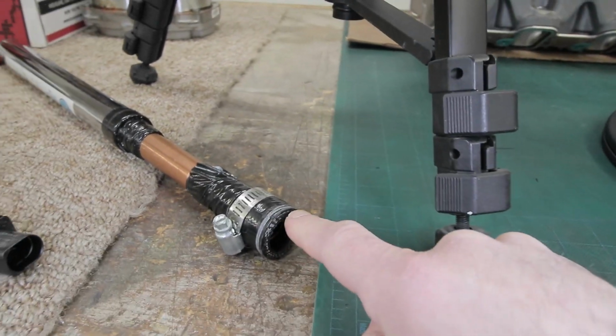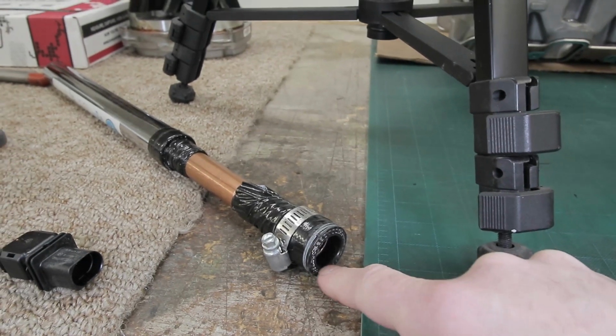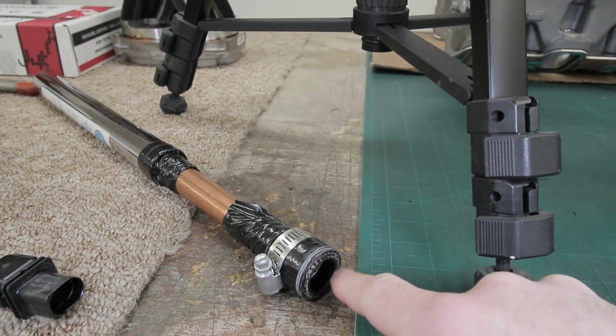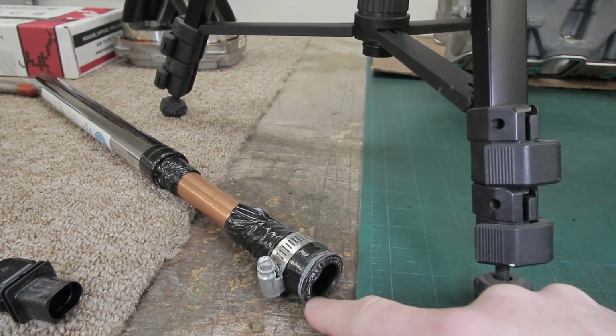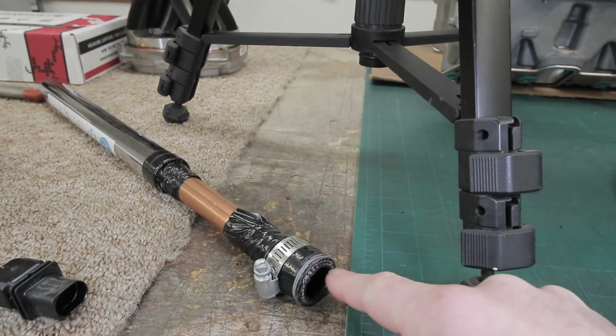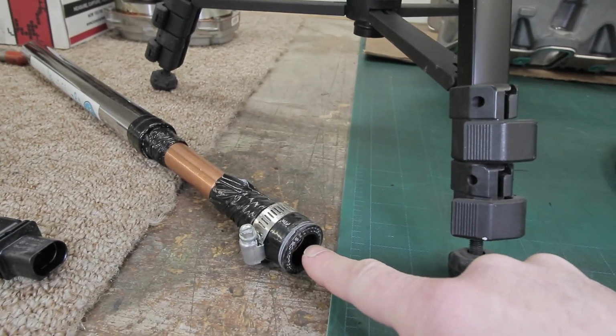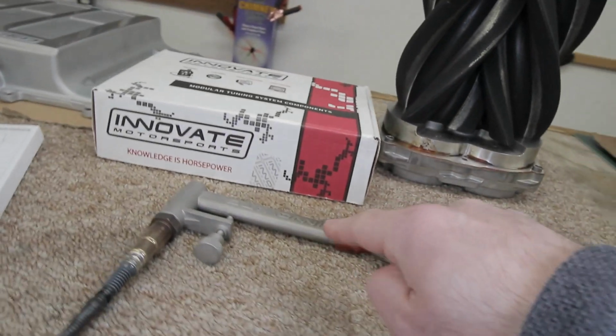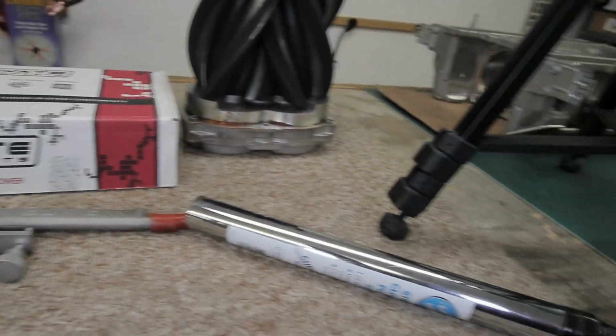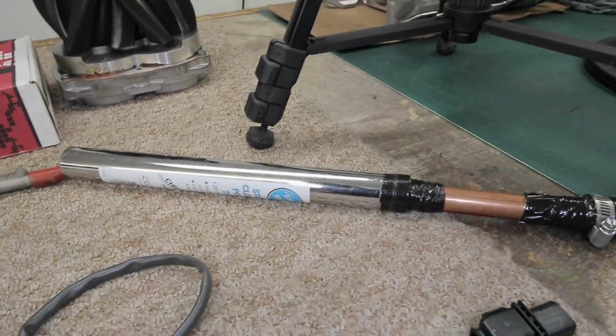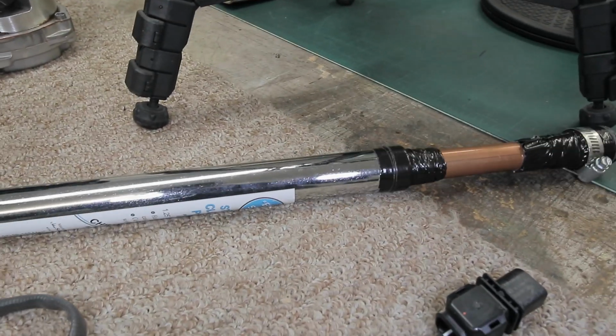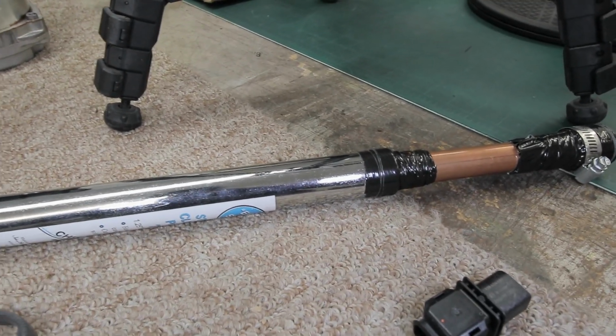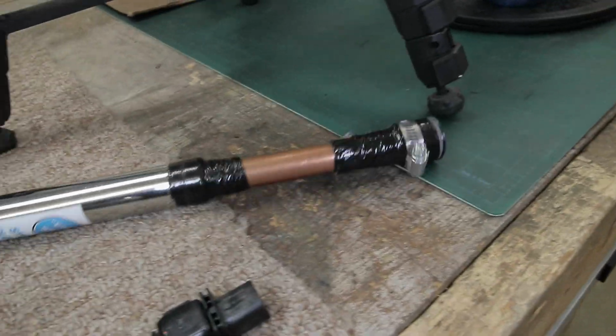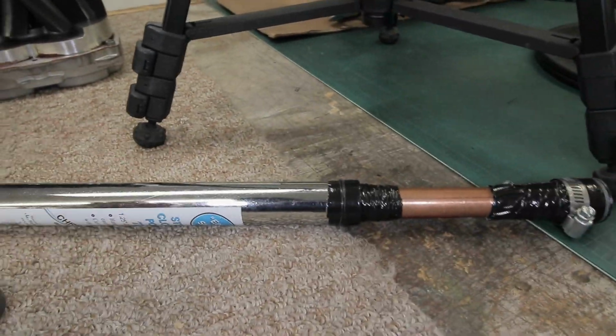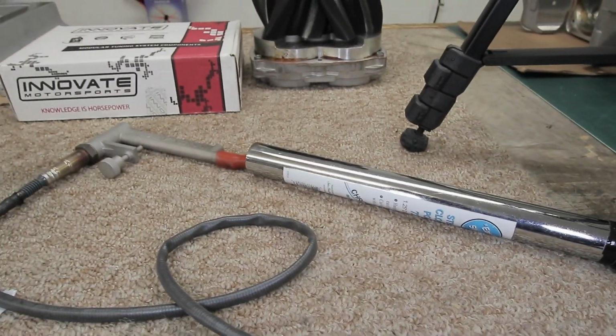Just so I can butt it up against the exhaust without doing any damage, on this end I have a piece of silicone coupler, so it won't melt. I'm going to press this up against the surface of the exhaust so it makes a sealing contact all the way around, and I'll get all the exhaust gases through the pipe and into the sensor. This works properly, I've already tried it on the machine, so I know it's going to work. But I couldn't get a good, stable reading without doing all this mounting and adapting to the sensor. You have to have the sensor buried deep inside the exhaust stream to get a reliable reading.